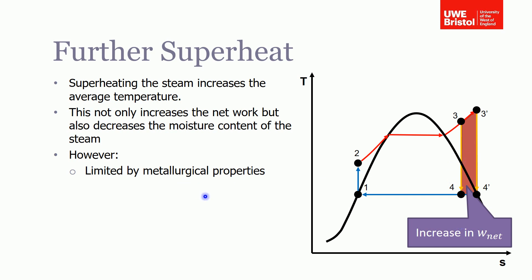However, you can't keep pushing the superheat temperature up indefinitely. What you're limited by are the metallurgical properties of the turbine materials — you can't keep increasing the turbine inlet temperature without advances in the materials used for turbine blades, particularly in the early stages of the steam turbine.